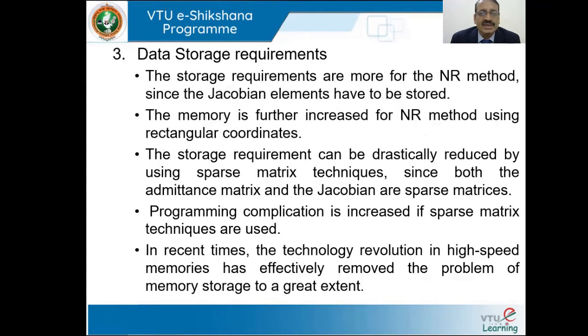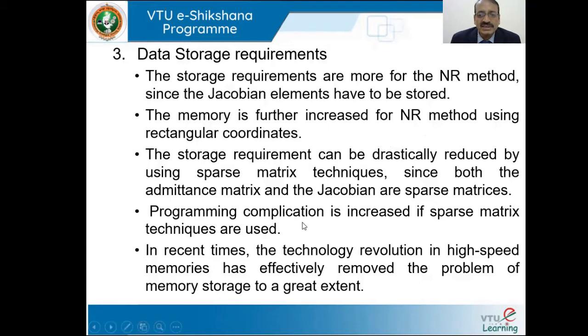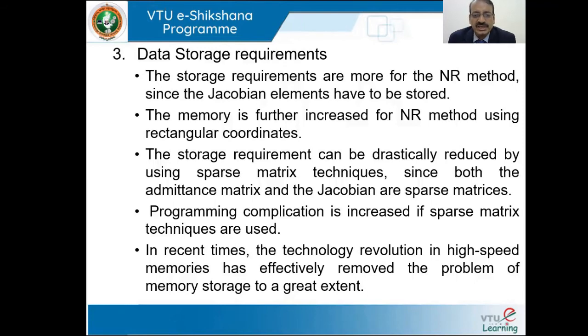Data storage requirements: the storage requirements for the NR method are higher as the Jacobian elements have to be stored. The memory is further increased for the NR method using rectangular coordinates. The storage requirement can be drastically reduced by using sparse matrix techniques. Since both the admittance matrix and Jacobian are sparse, we can use sparse matrix techniques, but programming complication is increased. In recent times, the technology revolution in high-speed memories has effectively reduced the problem of memory storage to a greater extent.